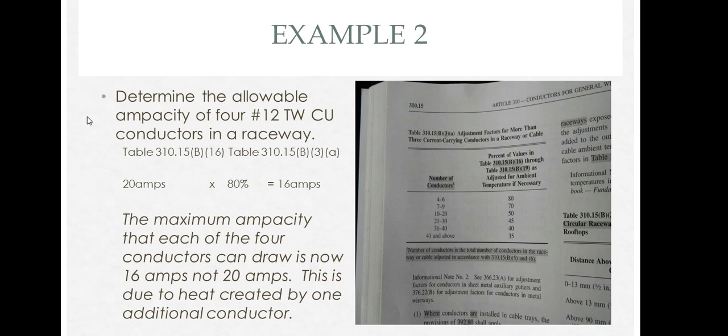In this first example, determine the allowable ampacity of four number 12 TW conductors in a raceway. From Table 310.15(B)(16), we get the ampacity of 20 amps. Because there are four current carrying conductors in a raceway, we must derate that ampacity by 80%. That adjustment factor is found at Table 310.15(B)(3)(A). Based on the quantity of conductors, you have to derate them a certain percentage.